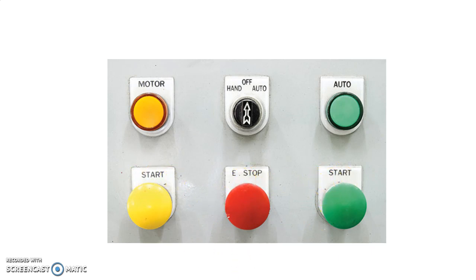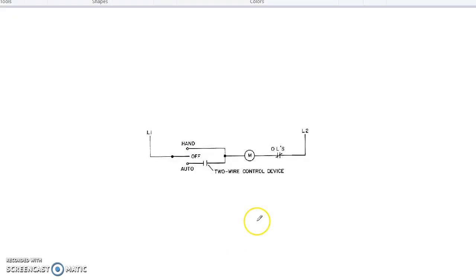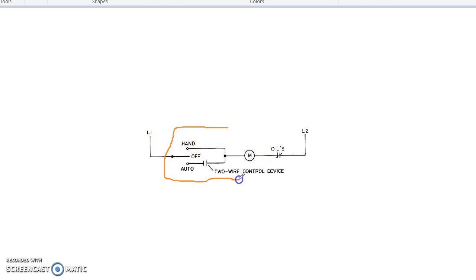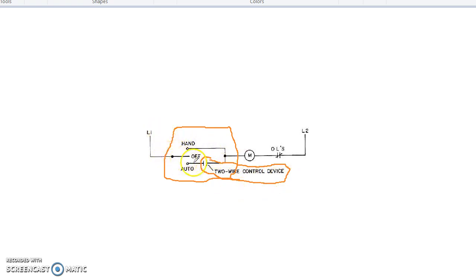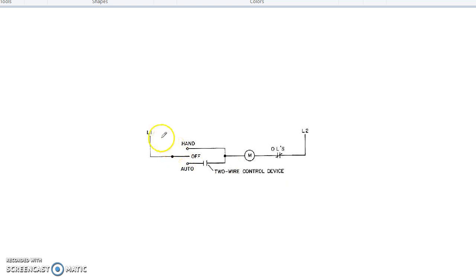Now we will go to the schematic diagram of the hand-off-auto. Basically, in schematic design, this is here the hand-off-auto. This is the signal coming from any control system, which let's suppose is SCADA. So this is the signal coming from SCADA to run the motor just in case the hand-off-auto is in auto, selected in the auto.